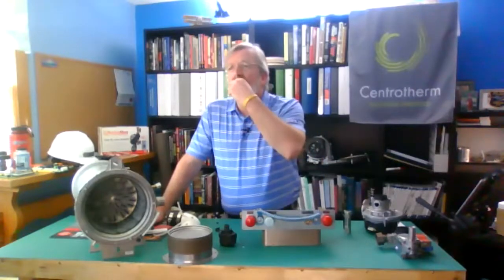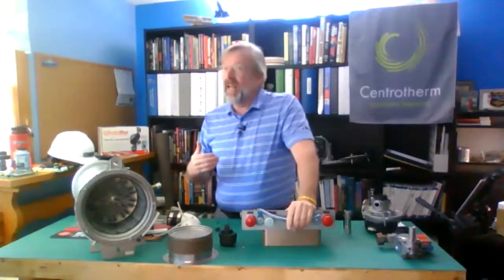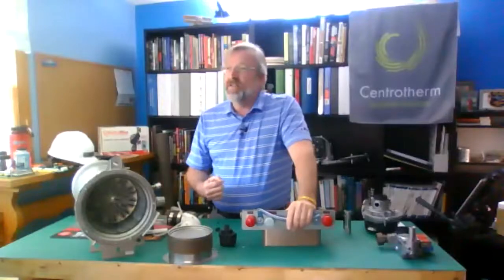Now, most water that we get, as far as on the potable side, what area are you in, Carl? Well, I'm outside of Boston, just north and west of Boston. Okay, so the MWRA water, so they pH balance that. They've done all of that. So usually we don't have to worry about it. For those that are on well water, that's more of a concern. The boiler side, pH, obviously dropping off because of glycol or any of that sort of stuff.